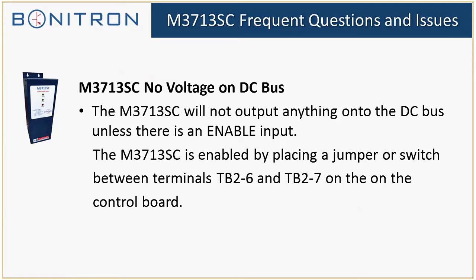So if you do have a larger amount of capacitance on your DC bus, even with an addition of DC bus capacitance, this thing can pre-charge it. So it's pretty solid. I don't really recall any real issues we've had other than just enabling the unit. And just like the 3712 single phase, basically you just need to have either a jumper or a switch between the terminals. The terminals will be TB2-6 and TB2-7 on the control board.